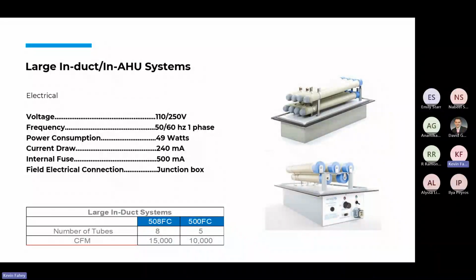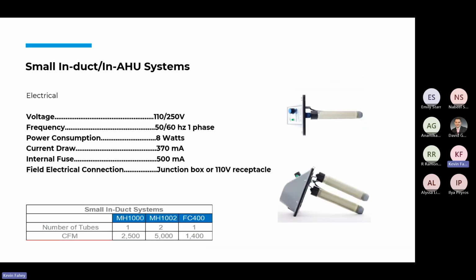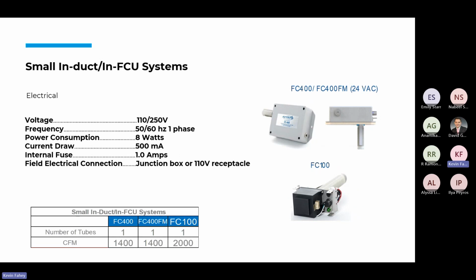And then we scale down to something that would be for a hotel room or a conference room, and I'll show you that in a minute. The next size would be 5 tubes that are 22 inches, good for about 10,000 square feet. Or we have another device with 5 tubes that are 14 inches that could handle up to about 8,000 square feet. And then for smaller systems, 5-ton and 10-ton systems, we have single tube or double tube devices. Again, the amperage draw and the wattage used is next to nothing for both of these devices. And then we have more compact ones for fan coils, water source heat pumps, PTACs, that go either inside the unit or inside of a small duct.